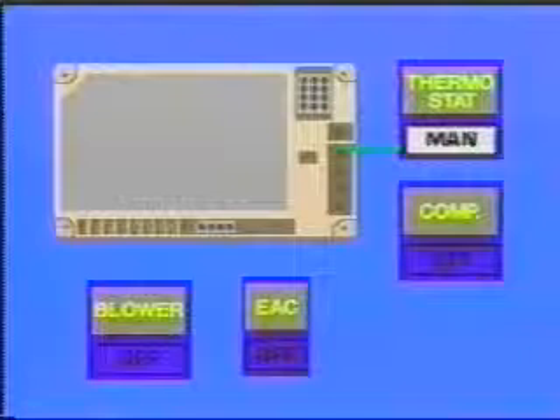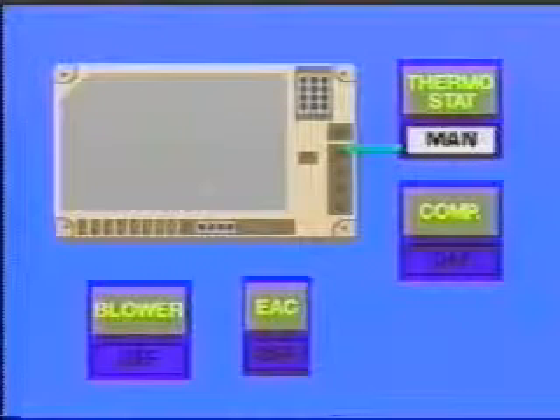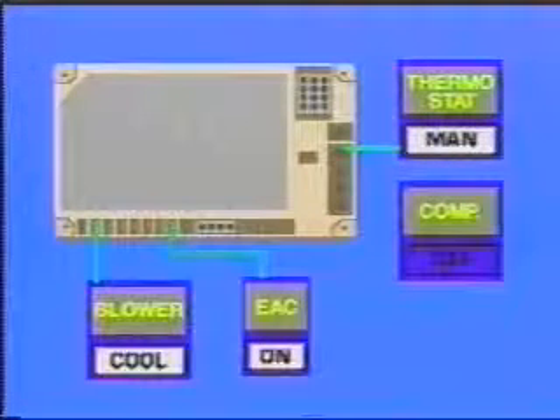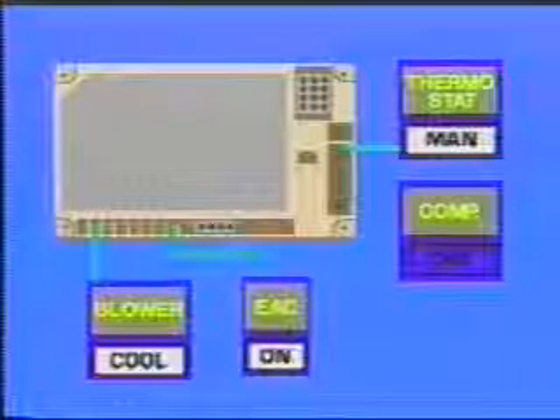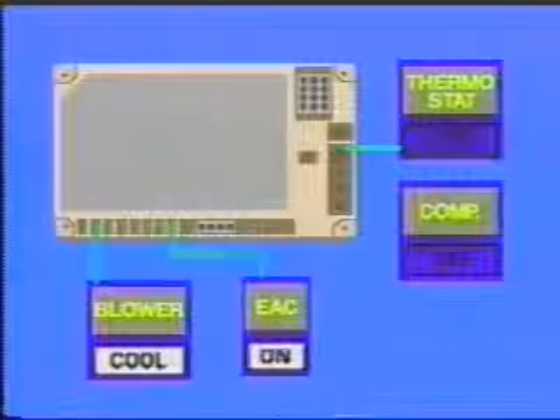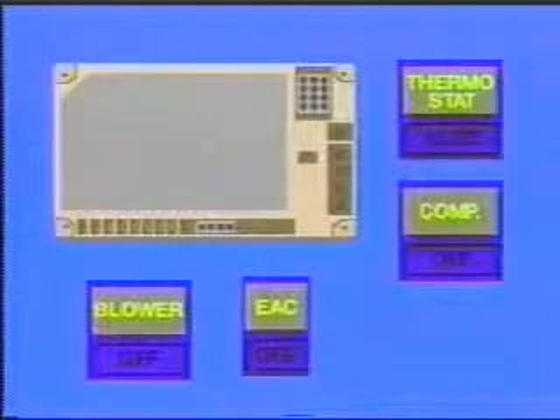When the thermostat fan switch is set to the manual position, the blower is energized on the cooling fan speed along with an optional air cleaner. When the switch is returned to the auto mode, both circuits are de-energized.